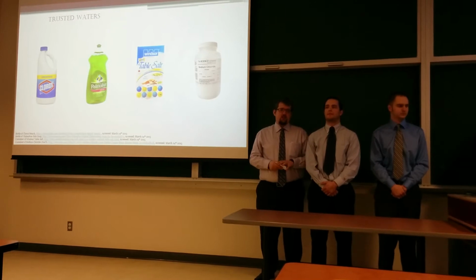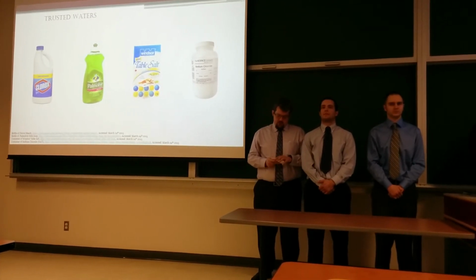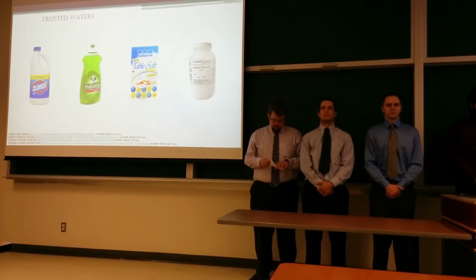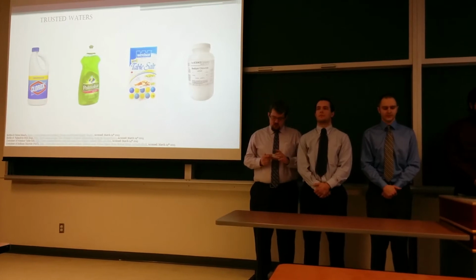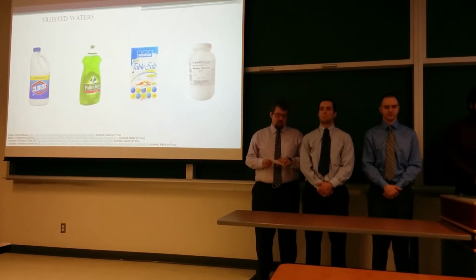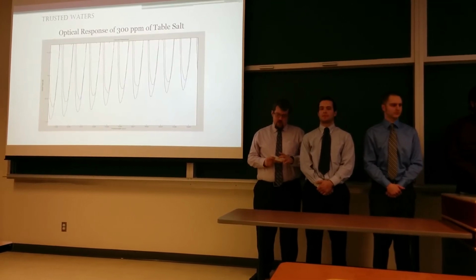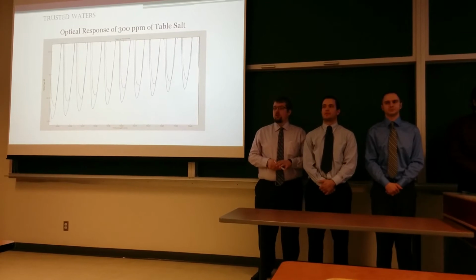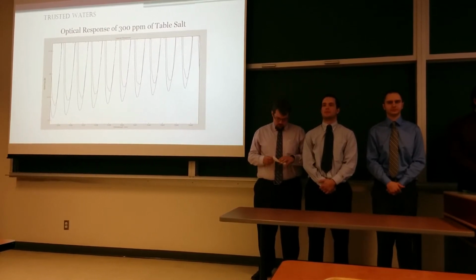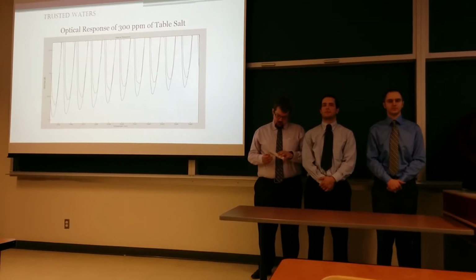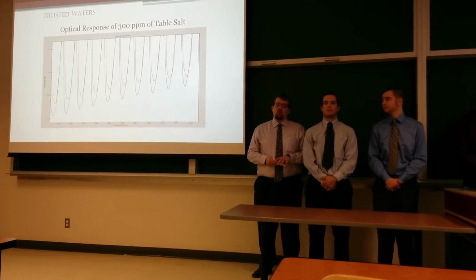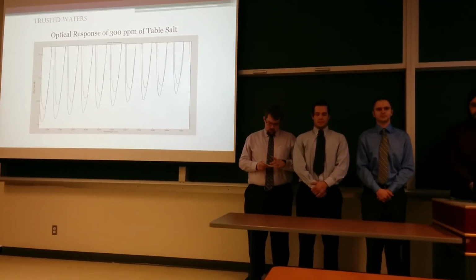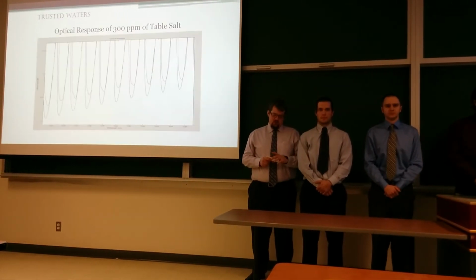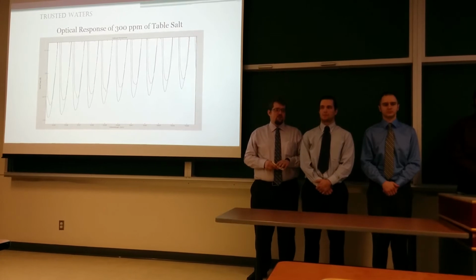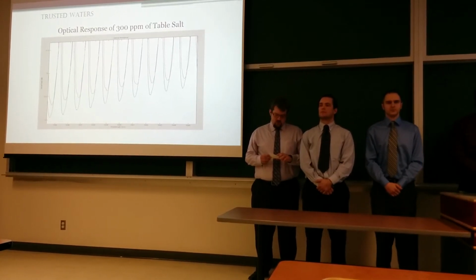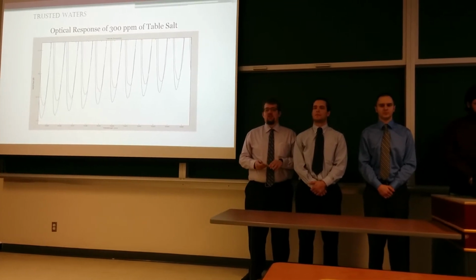These spectral shifts must be taken with respect to some optical baseline. This optical baseline is established by measuring the response of distilled water. Once this baseline was established, careful measurements were taken to determine known masses and volumes for each contaminant. These masses and volumes were then added into a known volume of distilled water to give the desired concentration for testing. The optical response of the contaminants at the desired concentration was then captured from the OSA and stored in the program for later comparison. This process was then repeated while changing the concentrations of the contaminants in the solution by adding additional volumes of distilled water. This method associates concentrations to spectral shifts, thus providing the calibration needed for the system.